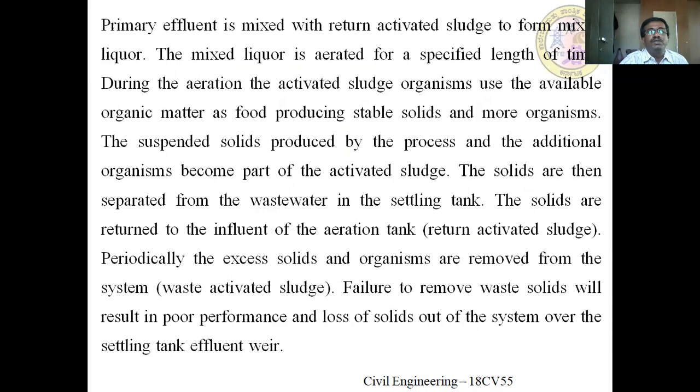So primary effluent is mixed with return activated sludge to form a mixed liquor. MLSS, usually termed mixed liquor suspended solids. The mixed liquor is aerated for a specified length of time. During the aeration, the activated sludge organisms use available organic matter as food, producing stable solids and more organisms. The suspended solids produced by the process and the additional organisms become part of the activated sludge. The solids are then separated from the wastewater in the settling tank, as I explained earlier. The solids are returned to the influent of the aeration tank as return activated sludge.